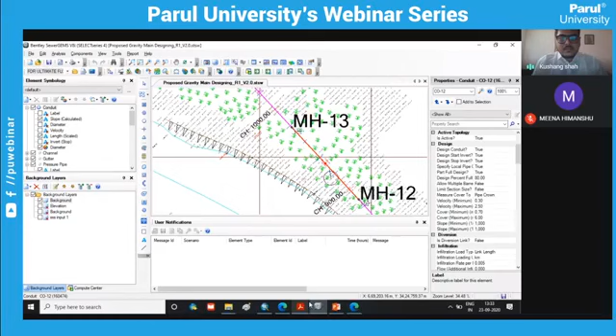Now after assigning the model, we need to go and check our results. I have already shown my diameter to you. That is one of the results which can prove that this could be the inner diameter which is required to accommodate that 31 MLD of discharge. Again, we have different choices of material for a particular pipe selection, so we need to compare them. We cannot directly fix the material for any location. We need to derive it: what could be the different parameters, different properties against which our material will survive.